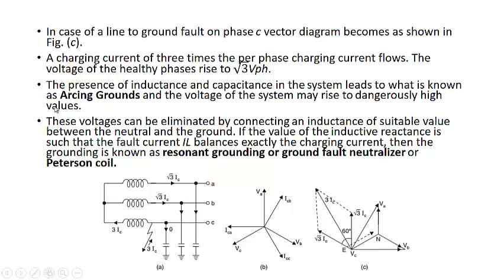There may be another thing: the presence of the inductance and capacitance of the system, that is inductance is this and capacitance is this, may lead to what is known as arcing grounds. The voltage of the system may rise to a dangerously high value. We'll see this in this case. So these voltages can be eliminated by connecting an inductance of suitable value between the neutral and ground. We'll see this also. If the value of the inductive reactance is such that the fault current IL, that is this current, balances exactly the charging current, then the grounding is known as resonant grounding, ground fault neutralizer or Peterson coil.